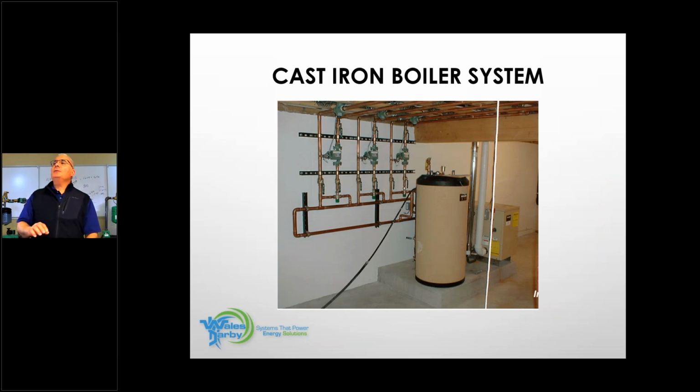So what I want to quickly go over here is the difference between cast iron systems and condensing. And not so much the difference is we could take a cast iron system that you see here with 3 water temps, 3 standard mix valves, and say that's only a 10 or 15-year-old system, and the homeowner wanted more efficiency. Can we make that more efficient? We can. We can add outdoor reset to that. We can do that with our Taco controls, the PC700 with any of our expandable controls.